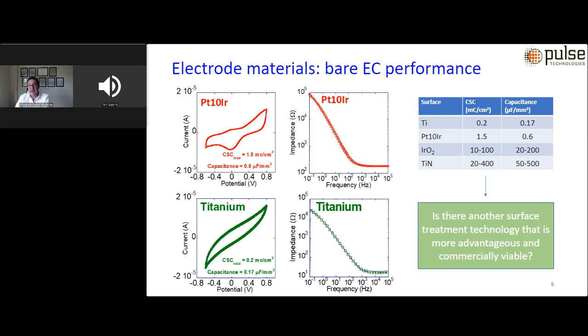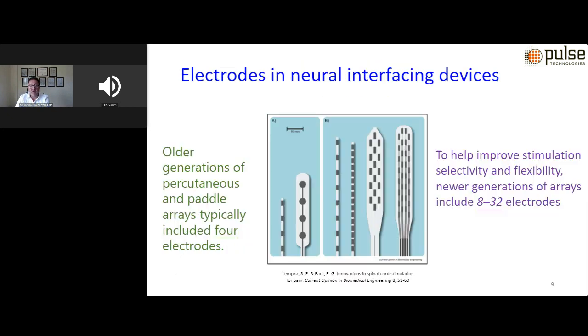From the CV and EIS plots that I'm showing here, you can see that platinum iridium charge storage capacity total is around 1.5 millicoulombs per centimeter squared, and its specific capacitance is around 0.6. And those same parameters or performance metrics for titanium are around 0.2 and 0.17 on average, and that's why titanium is much poorer compared to platinum iridium. So another question that I'm posing here is, is there another surface treatment technology that is more advantageous and commercially viable in order to enhance the electrochemical activity of the electrodes in the body? And I hope that I will be able to answer this question by the end of the presentation.